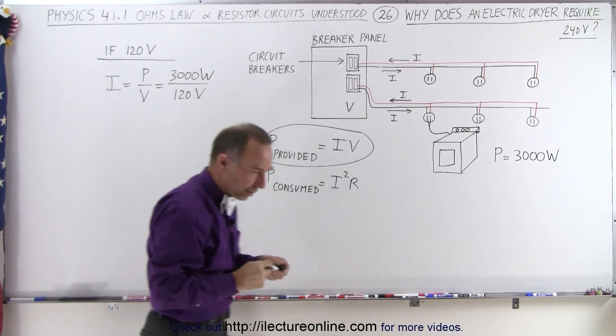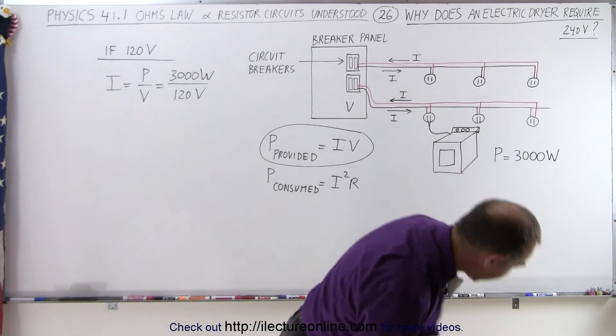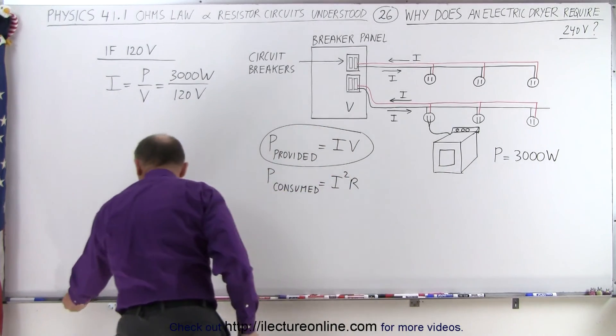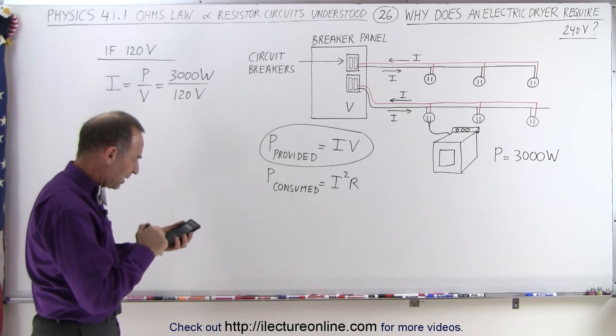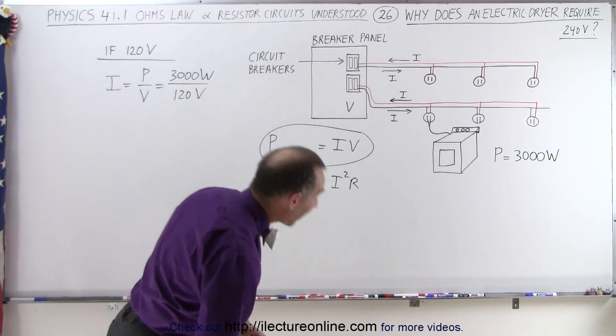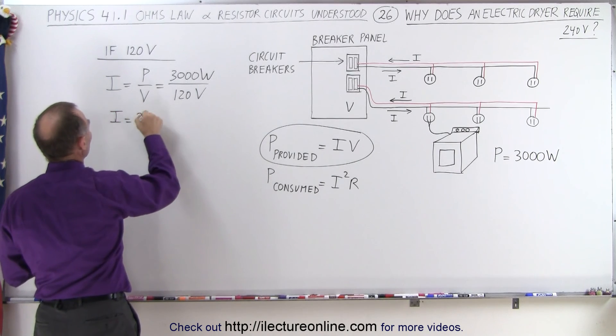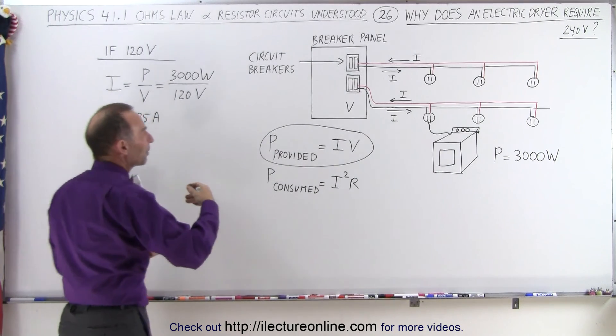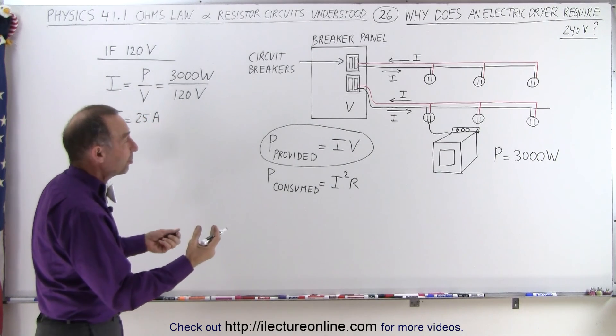Let's see how many amps that would require to run that. If I can find my calculator, I would be happy - it's right over here. All right, so 3000 divided by 120, well that's 25 amps. That's a lot of current, so I required would be 25 amps. So the typical 15 amp or 20 amp breaker would not be sufficient.